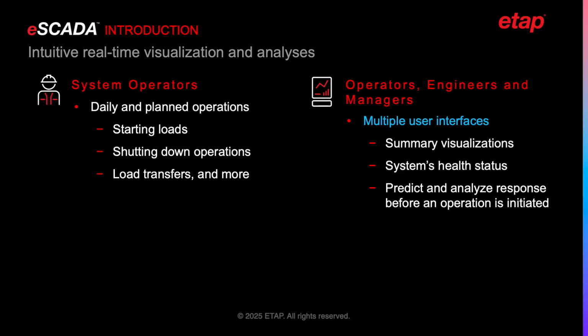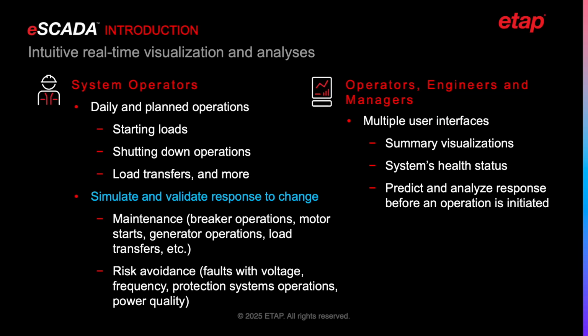The eSCADA solution also provides multiple user interfaces for operators, engineers, and managers so they can easily visualize a summary of the electrical operation and its health status. This solution also provides a tool to predict and analyze the electrical system response before an operation is executed. When an operator needs to perform changes in the operation and maintenance, such as a breaker operation, motor starts, generator operations, load transfers, and more, they can simulate and validate the response of the electrical network and understand risk and avoid unforeseen conditions, such as faults, voltage, frequency, protection system operations, and power quality issues.